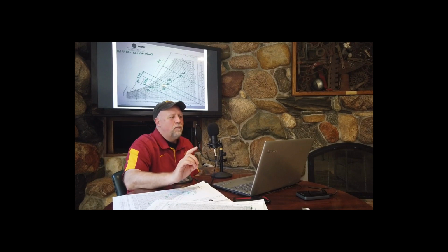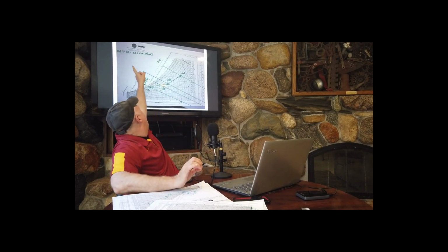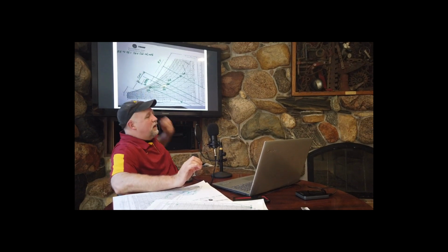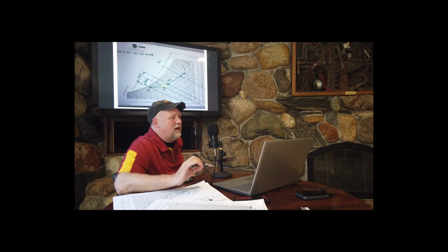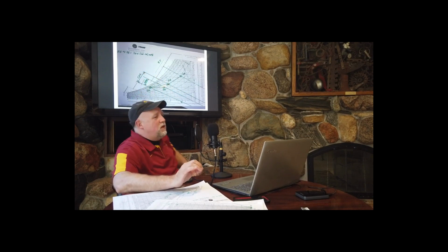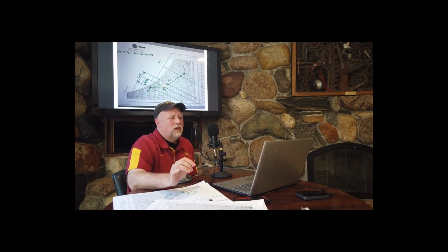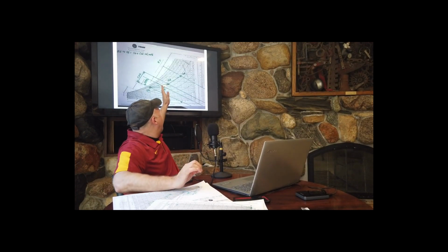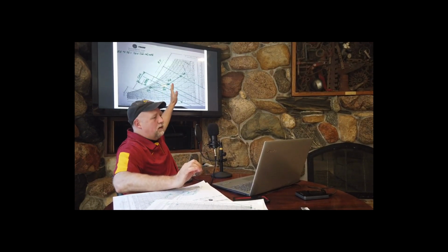You determine mixed air. All right, mixed air, the dry bulb temperature of the mixed air is the dry bulb temperature of the return air plus the difference between the outside air and the return air. And you take that difference times your mixed air percentage. In other words, if 10% of the total is outside air, then we are 10% of the way towards there.